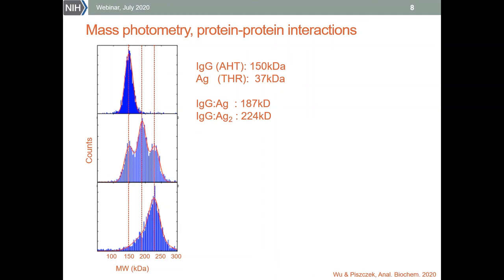Here I am showing you data for the IgG antibody binding human thrombin — these are the first mass distributions we obtained for the system when trying different things on our new mass photometry instrument. On the top panel we have the antibody alone at a concentration of about 25 nanomolar. As you can see, it is a clean preparation with mostly a single 150 kilodalton peak.